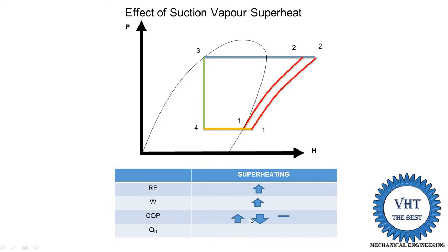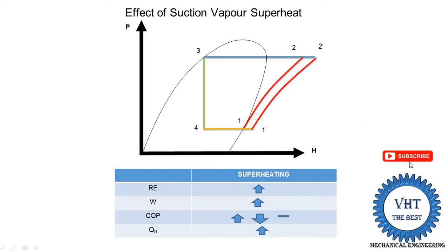For example, if we use R12, the COP is increased. If we use R22 or NH3, it may be reduced. So depending on the refrigerant and pressure range, COP may be increased, reduced, or constant. Regarding heat rejection in the condenser: in the earlier case the line is smaller, H2 minus H3. After superheating, the length is increased for H2-dash to H3, meaning heat rejection in the condenser is increased.